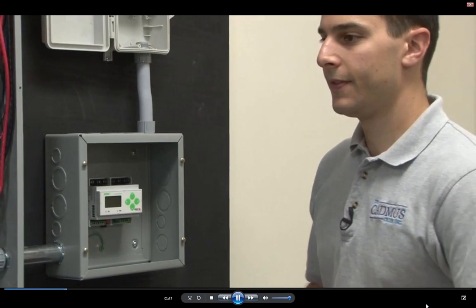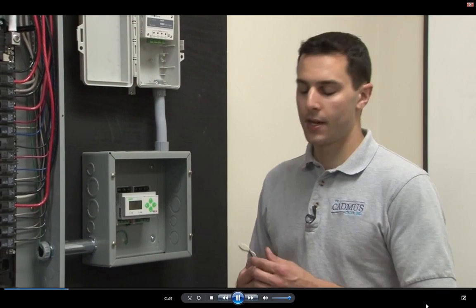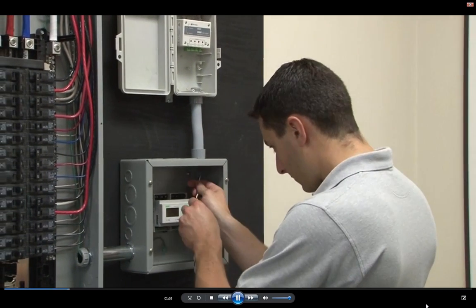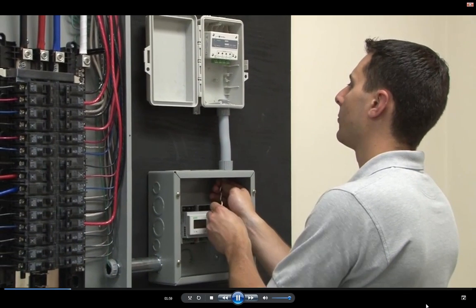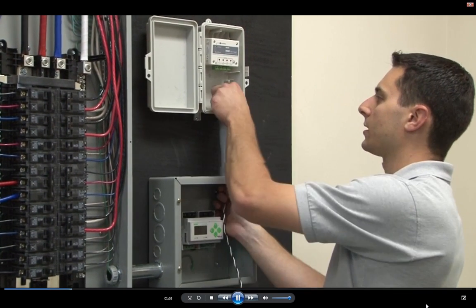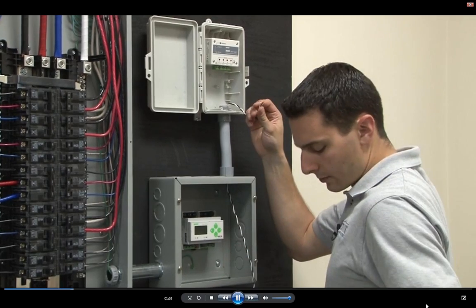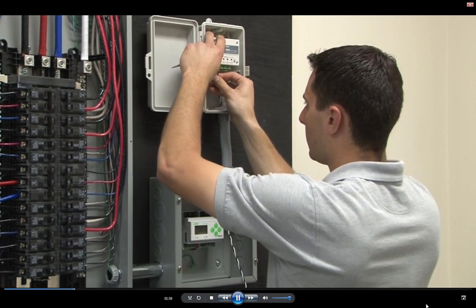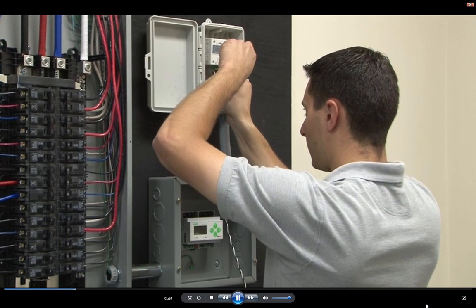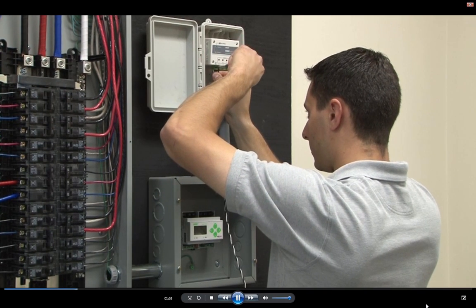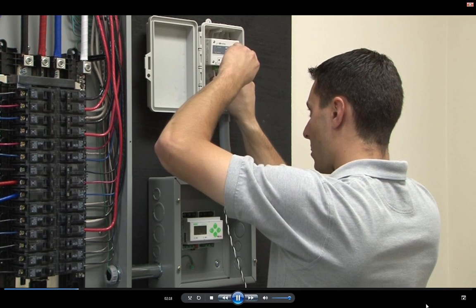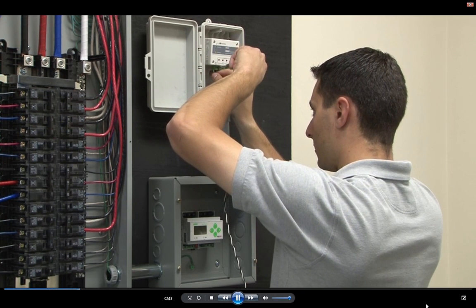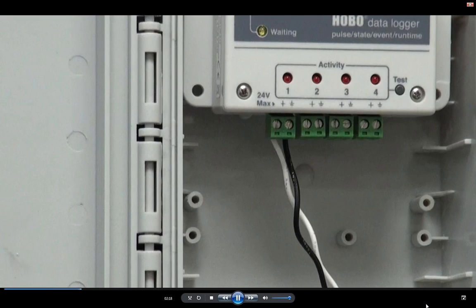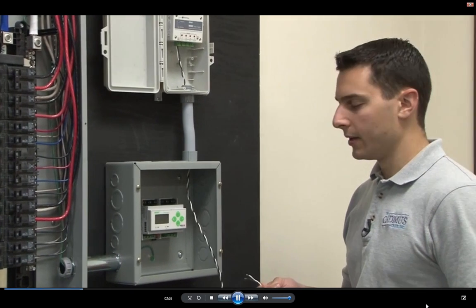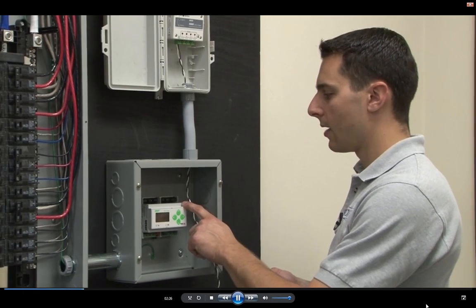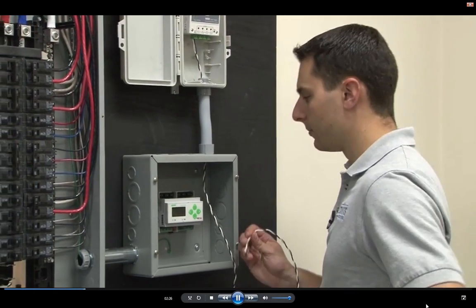For this, we'll use the E50B2 lead set available from Onset. We'll run the black and white conductors up to the UX120. We'll start with channel 1 on the UX120. And we'll connect the channel 1 lead to the volt amp reactive hour terminal on the E50B2.